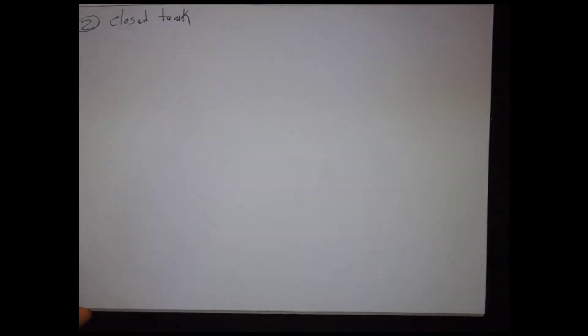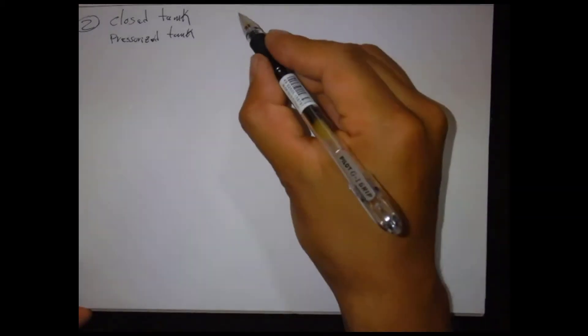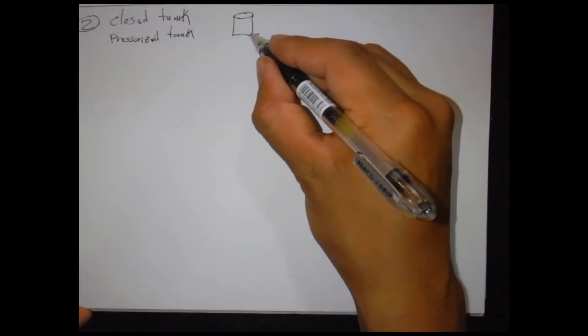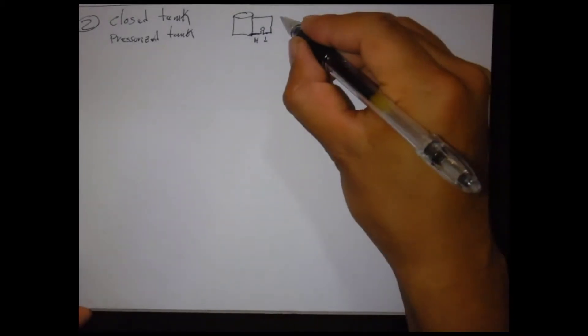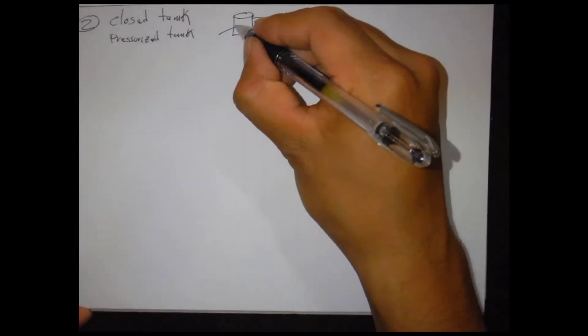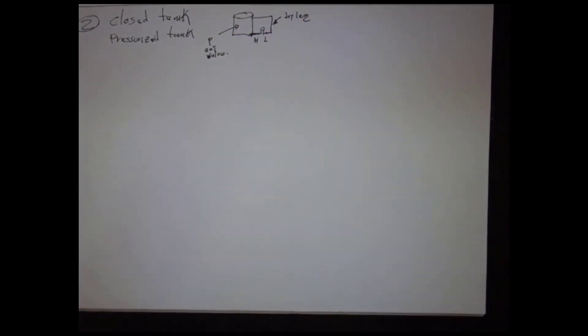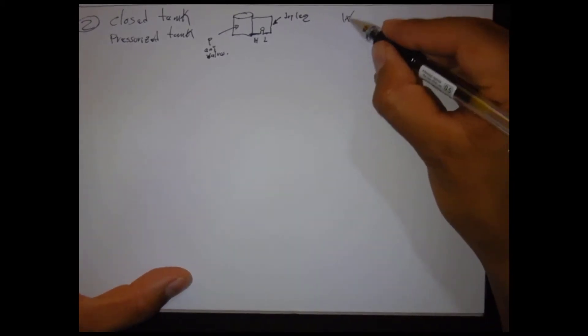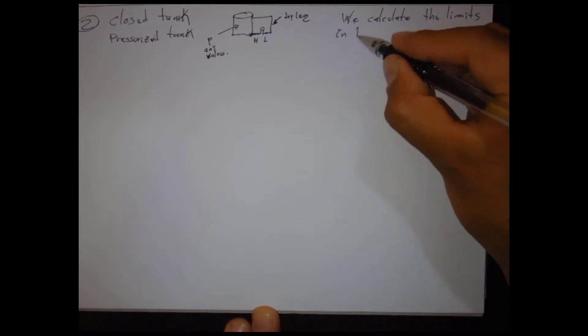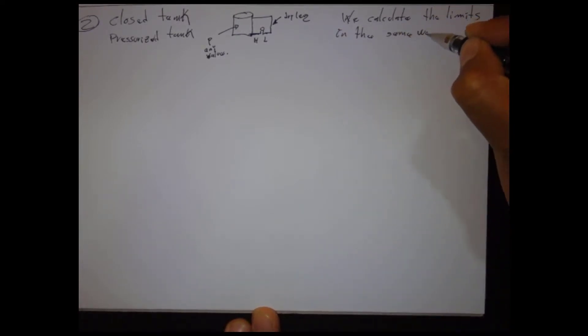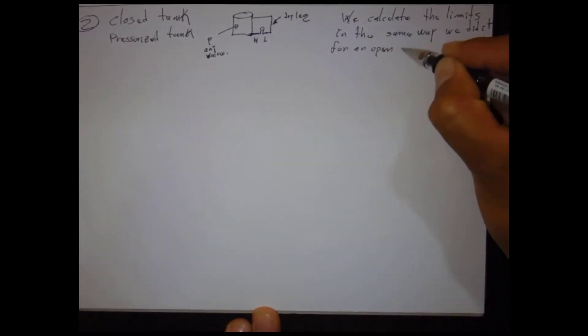Case number two: a closed tank, which we can see as a pressurized tank. To measure the level inside a closed tank, we need to connect the low pressure side to the top of the tank. This pipe could be either full of the liquid in the tank or completely empty. These cases are named wet leg and dry leg respectively. For the dry leg case, we calculate the level of the liquid in the same way as for an open tank, and remember to keep the dry leg without liquid.